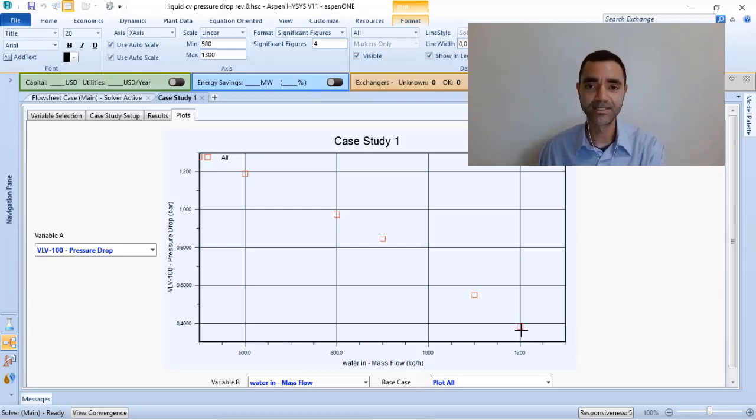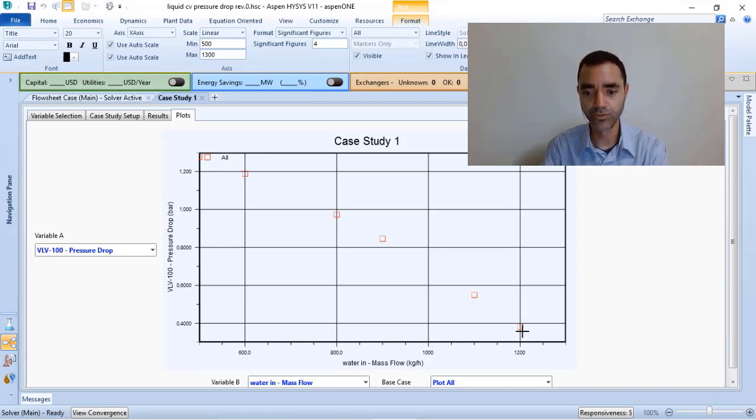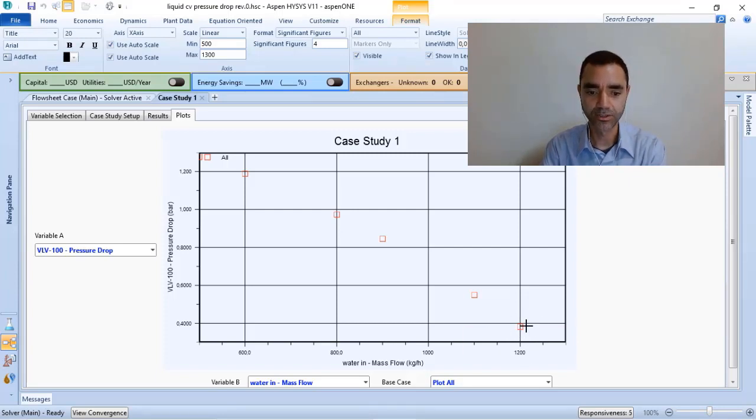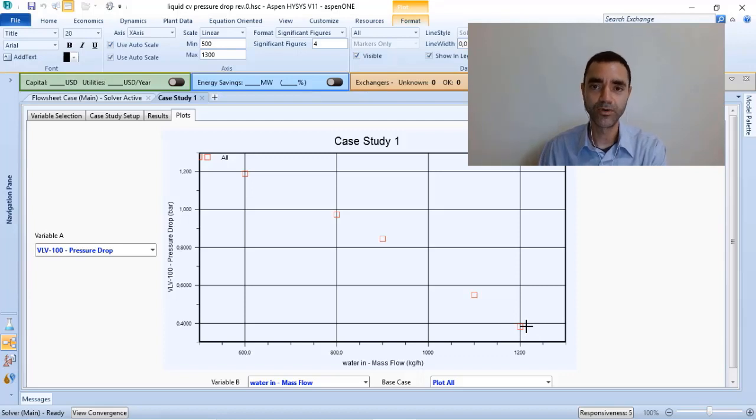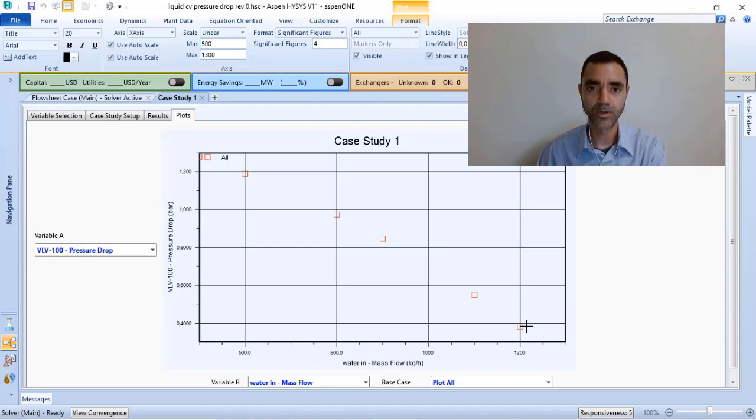The paper says that to do the right selection of my control valve, I need to consider the maximum flow and the resulting pressure drop. Based on that, I will have the calculation of the CV, and I will choose the CV as close as possible to the calculation.